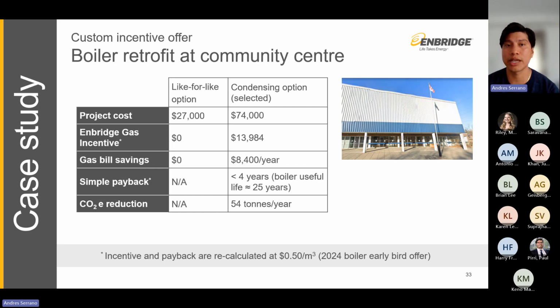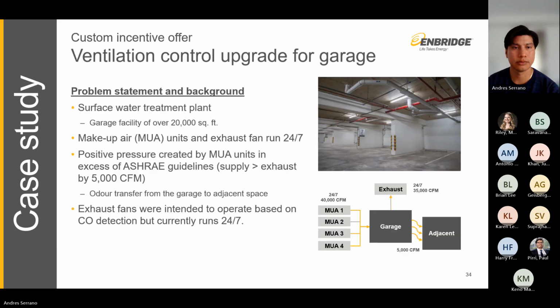Once we look at a simple payback, we estimated that the condensing option will have a 4-year simple payback. What this means is that after year 4, the customer will start realizing those savings up until the boiler reaches its end of life, which we estimate to be 25 years. And that wraps up that case study.